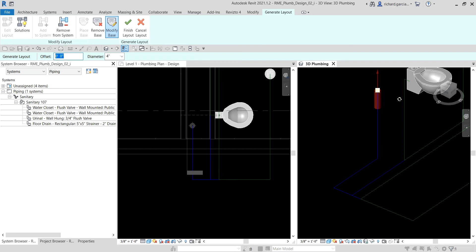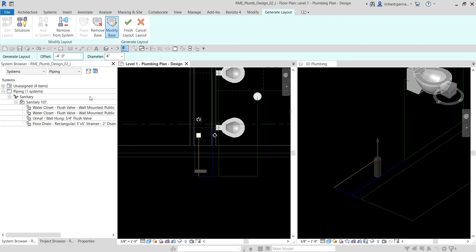I also want to change the offset to a negative value — let's say minus four feet. So I type minus four, meaning that pipe will go to minus four feet. We still have a problematic pipe, but don't worry. The elevation of the base relative to the other components in the system is very critical — the elevation must be specified low enough to allow sloping of the sanitary piping.